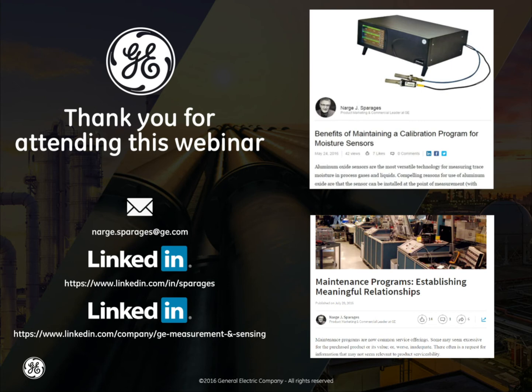on somebody's shelf. And again, that's where a good calibration program helps: you probably don't want freshly calibrated probes sitting on a shelf. What you probably want is those freshly calibrated sensors in your application. The ones that are slightly out of calibration could either be on the shelf as a backup or in rotation going back into the factory for calibration to be put in another application. There is a benefit, obviously, of keeping sensors in their own applications, but if you're looking for strict accuracy and recent calibrations, cycling them through is not an issue. That is something that is fine for the customer base.